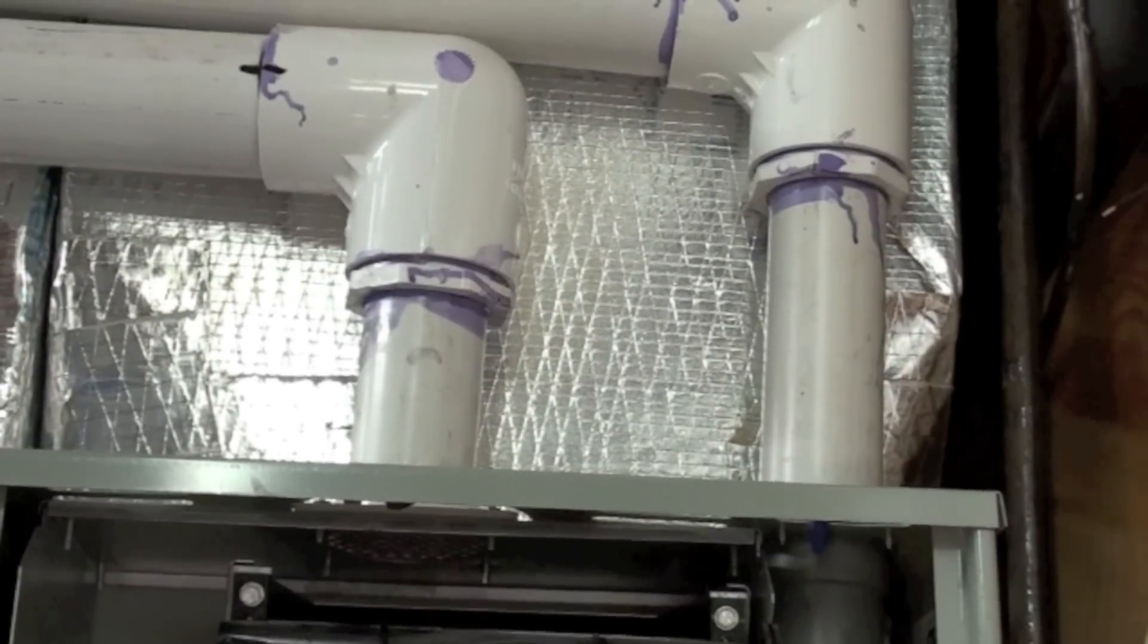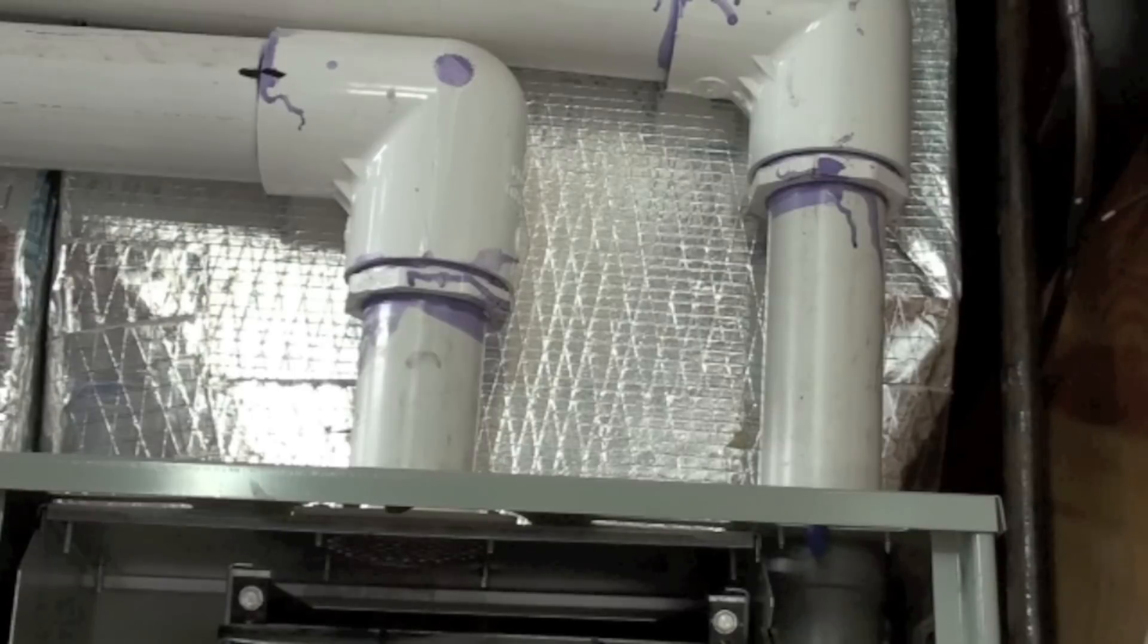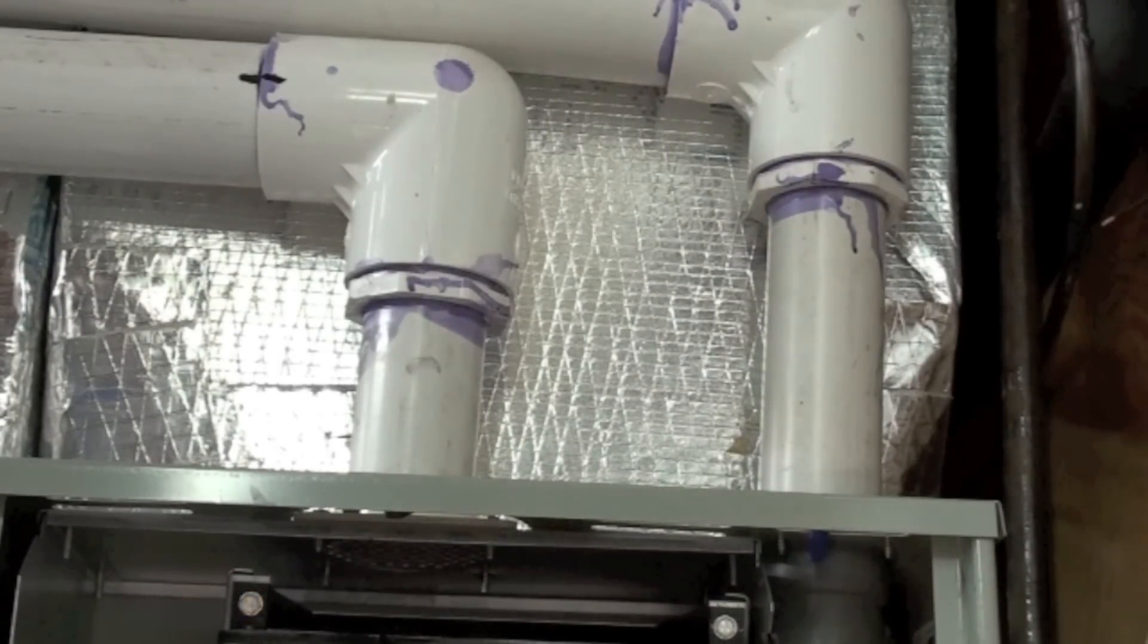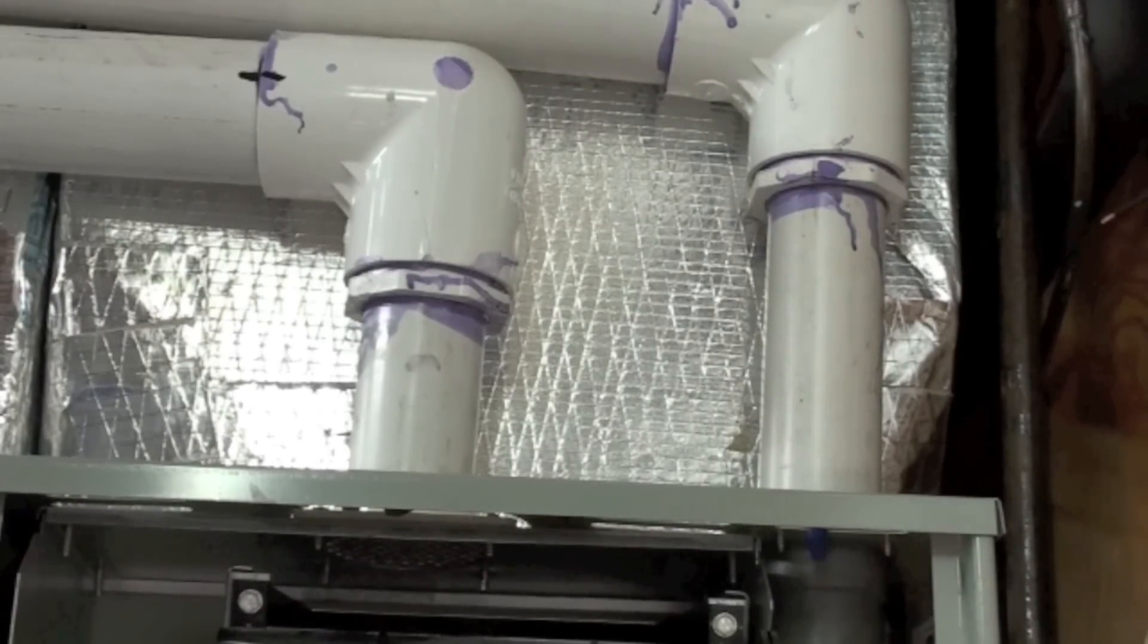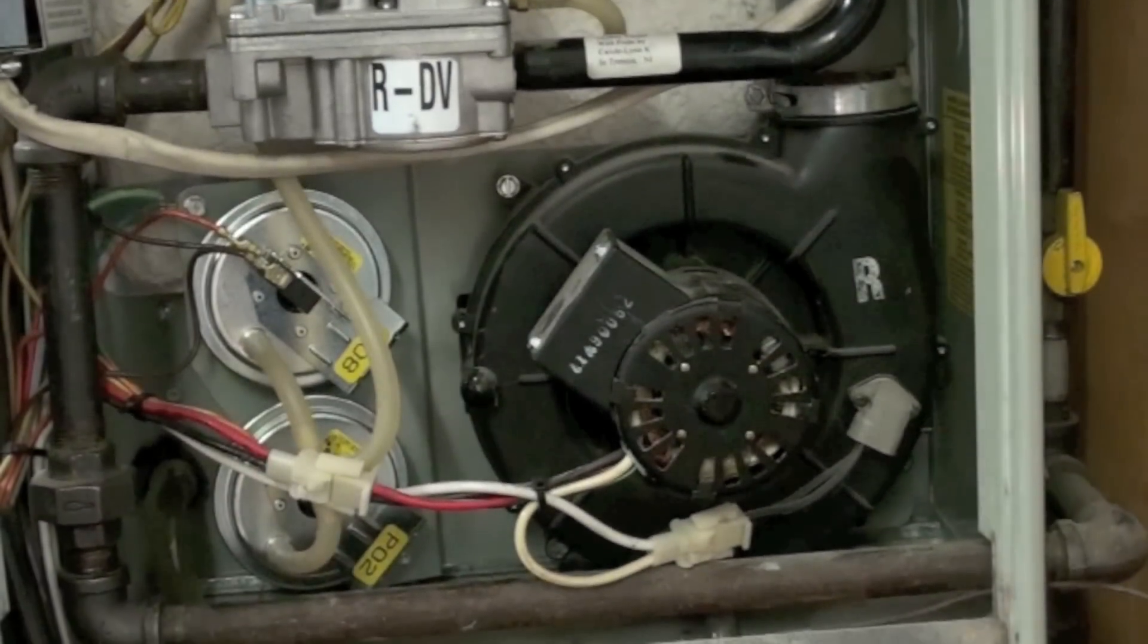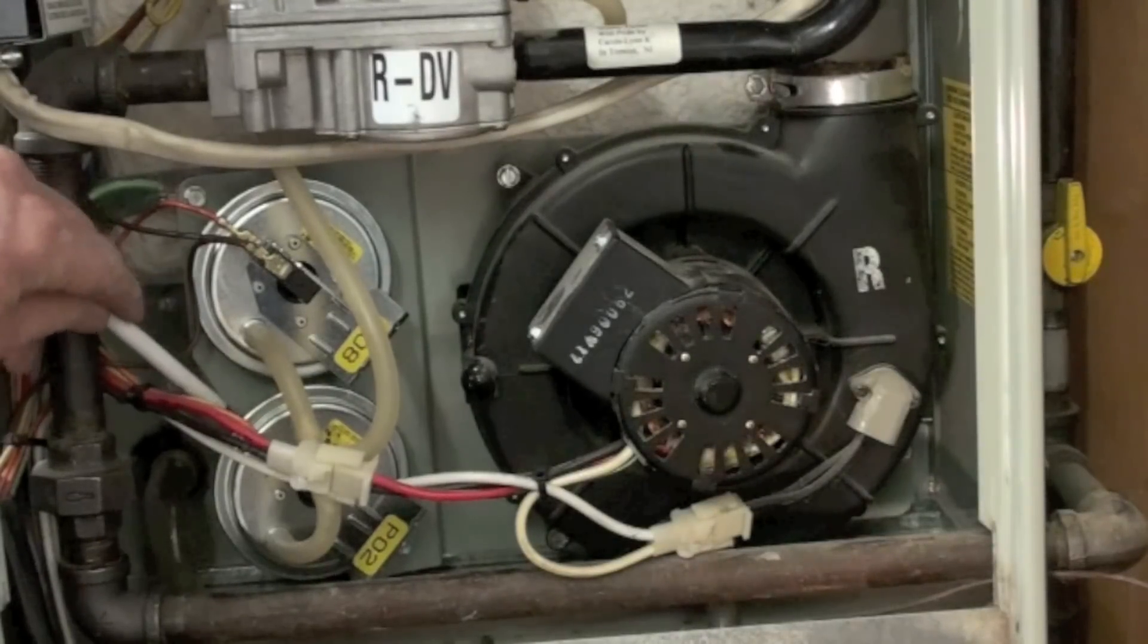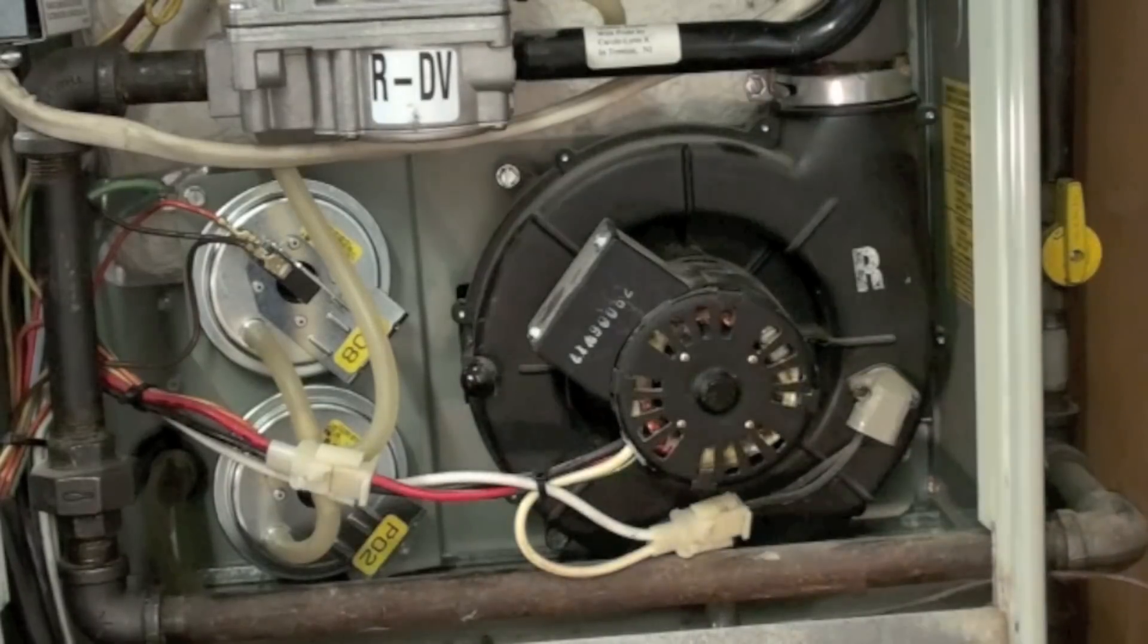If your integrated furnace control says there's a pressure switch problem, then you got to start looking at things like venting. Is the outlet plugged? Is the inlet plugged? Is there snow in it? Is there a screen in it and the screens are dirty or got ice on it? All these things can cause short cycling on these machines. Don't always just blame that little old pressure switch because it is just a signal. It's a little signalman telling the control that there's something wrong in the furnace.